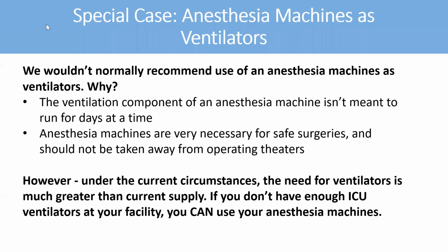Yep. Okay. This is another way to get an extra ventilator. Basically, during COVID, the ventilators in your ICU department may be overwhelmed, and you need another ventilator to use. So this is another way of doing it: your anesthesia machine can be converted into a ventilator. It is basically to run for a short period of time. You can use them as a ventilator. But you need to understand that when you use an anesthesia machine as a ventilator, you need to make sure you have an HME filter, because anesthesia machines don't have a humidifier, since they are a closed loop circuit. So you need to look into that particular part.